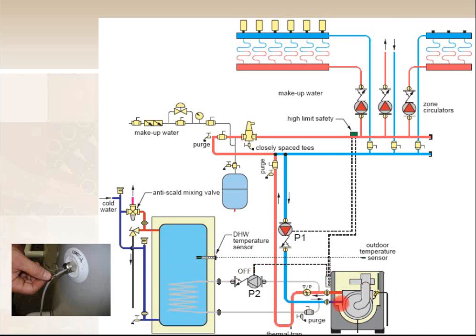I already got this boiler running. I can use that boiler to heat my domestic water if I want as well. So an indirect tank basically looks like a water heater. It's typically a vertical tank, well insulated. There's 3 major things different. 1, there is no burner on the bottom of this guy, right? Instead of a burner on the bottom, we have a hydronic coil in here. And he's just getting hot water from the boiler, running it through the coil, and returning it back. That water in the coil never touches the domestic water in the tank.